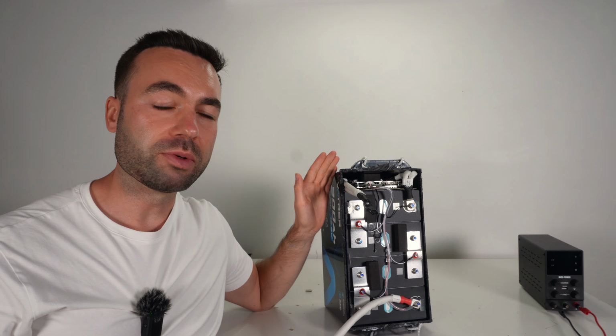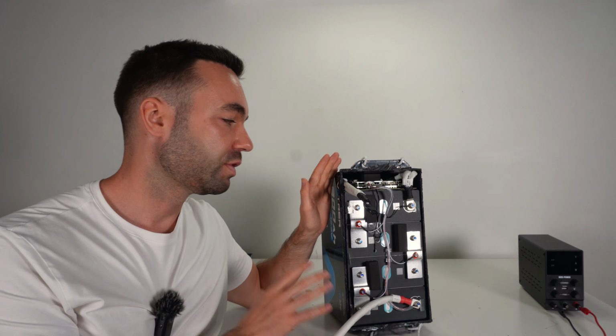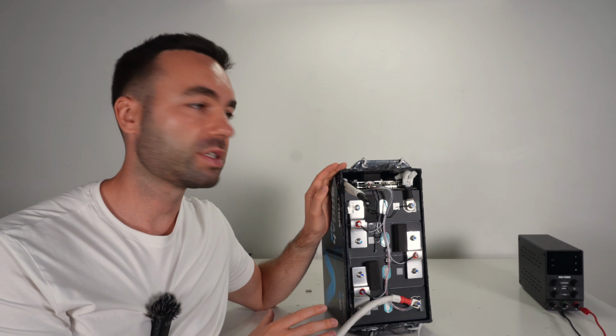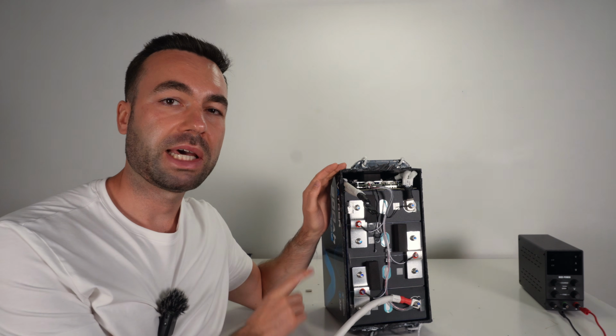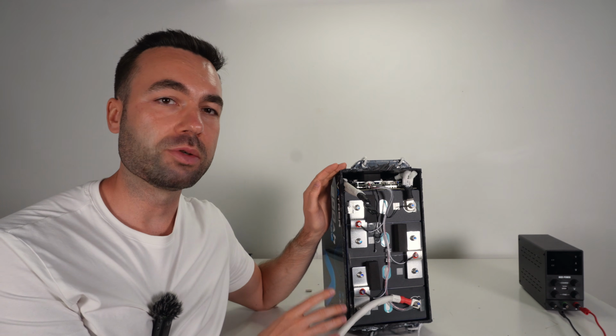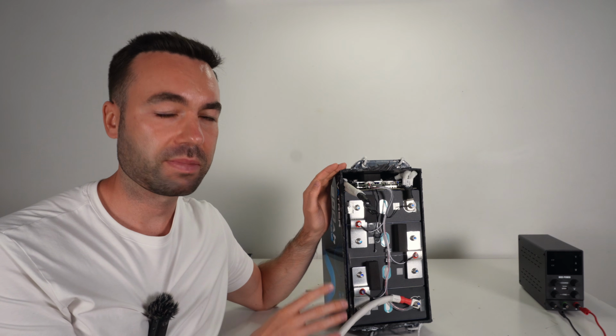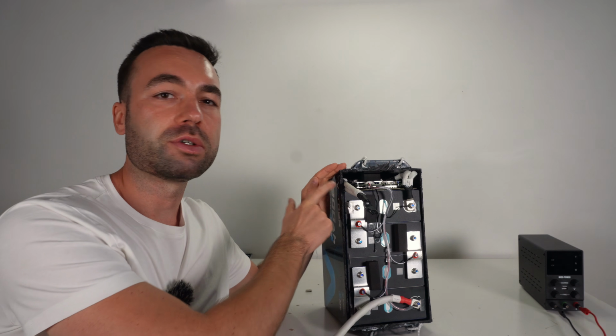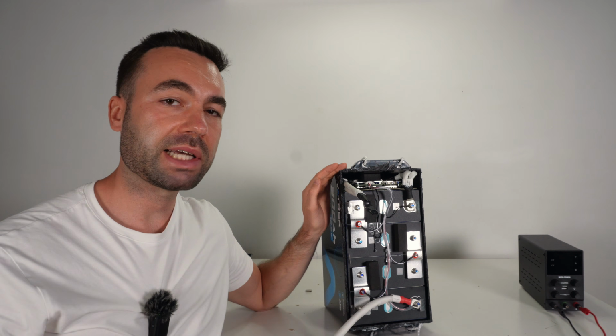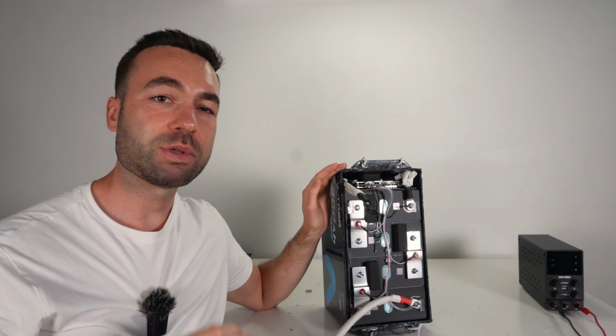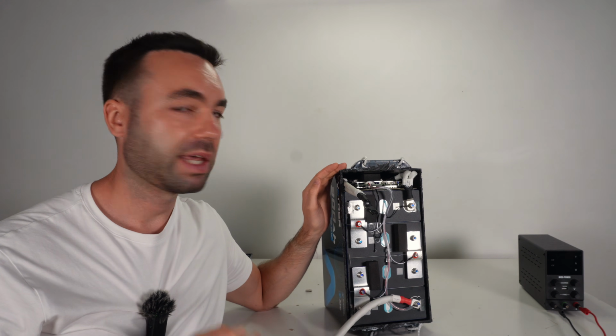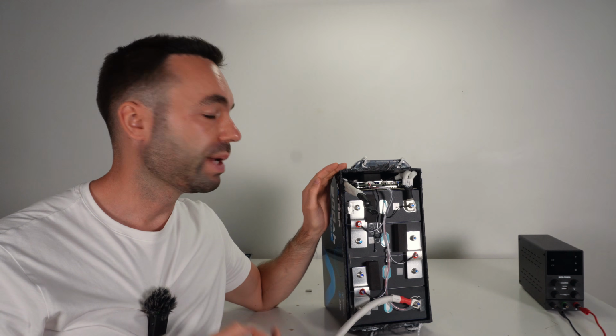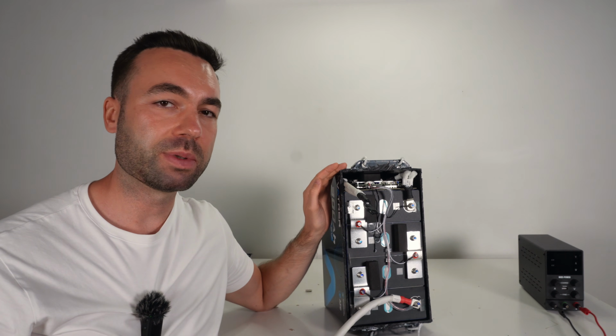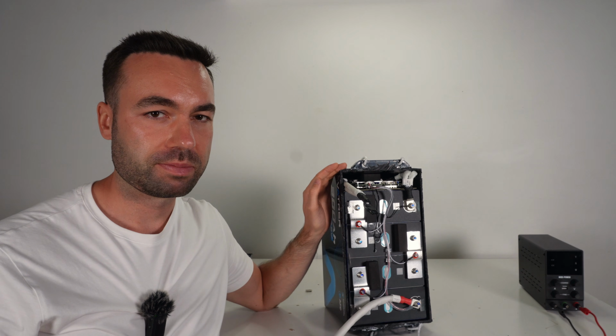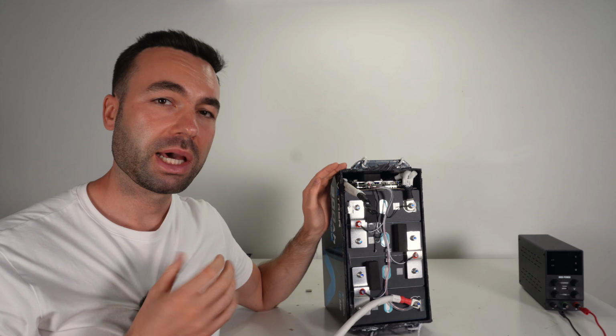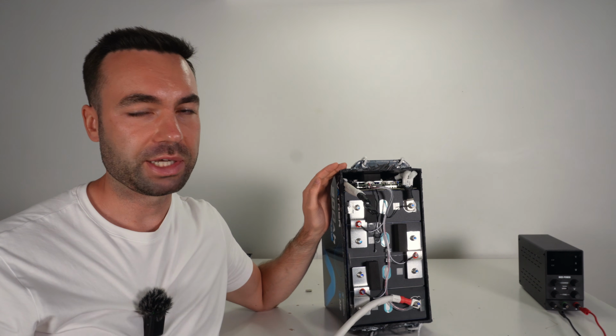So you will only reach a high voltage of 3.75 volts if one of the cells is high, and that's during an imbalance. However, the 200 milliamp balancer inside the BMS is able to clear an imbalance. In my case, it was gone in less than 1 hour during absorption. So personally, I wouldn't worry about this issue.